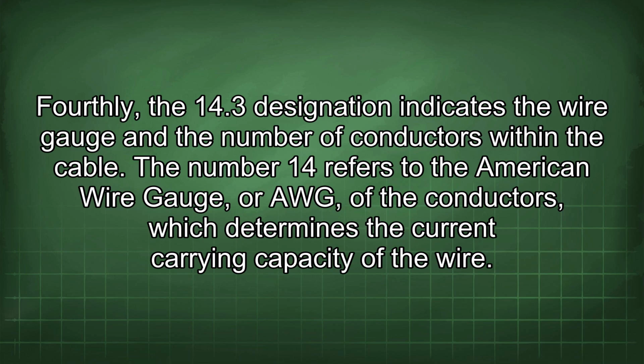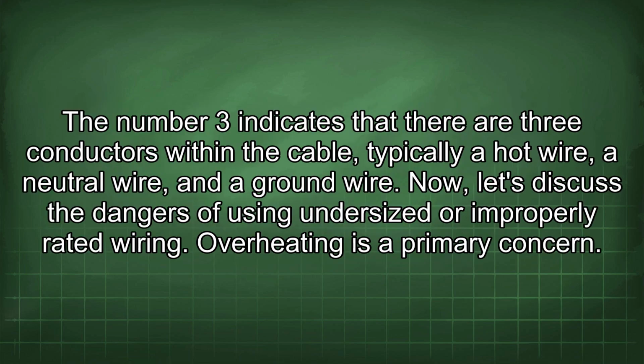Fourthly, the 14.3 designation indicates the wire gauge and the number of conductors within the cable. The number 14 refers to the American Wire Gauge, or AWG, of the conductors, which determines the current carrying capacity of the wire. The number 3 indicates that there are 3 conductors within the cable, typically a hot wire, a neutral wire, and a ground wire.